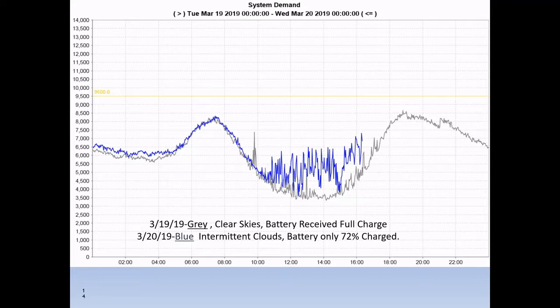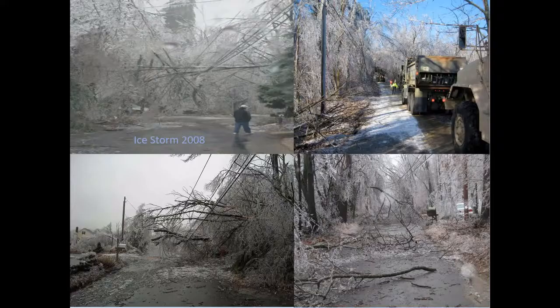This shows batteries on a clear skies day — the day before was 3/19/2019, clear skies, battery at full charge. One of the lessons learned is to watch the weather. We've got to understand this is using the solar, and we have to make sure it's going to be available the next day. Some days we're charging but not discharging as much at night because we need to save for the next day. On one day we only got a 72% charge because of intermittent clouds, even though the forecast called for another sunny day. That's where MWEC comes in great — they're monitoring the weather, loads, and the ISO forecast.